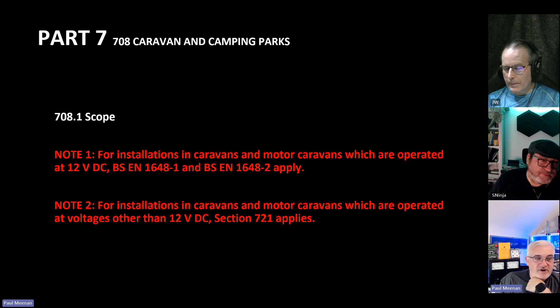708 again, the means of connection between a caravan pitch and leisure accommodation vehicles should be an assembly of the following, and there's a new part, section B, on this regulation: a flexible cable of continuous length, 25 metres plus or minus 2, having a harmonized code designation of H05VV-F to BS EN 50525-2-11, or H07RN-F to BS EN 50525-2-21, or equivalent, incorporating a protective conductor with conductors identified according to Table 51, the cross-sectional area in accordance with Table 721, and an outer sheath coloured orange.